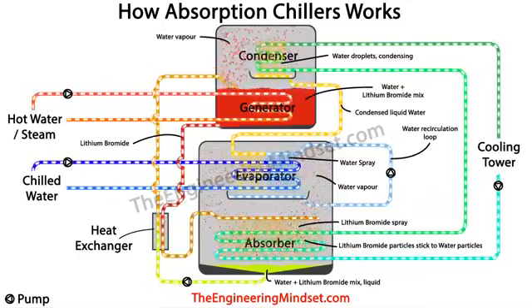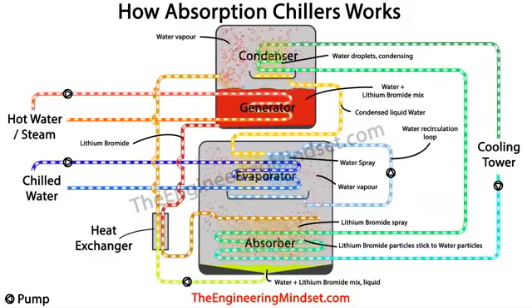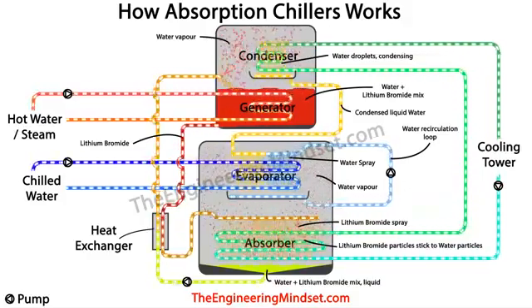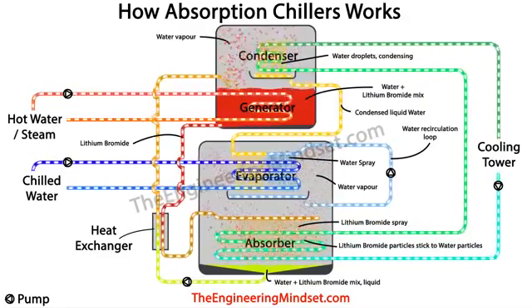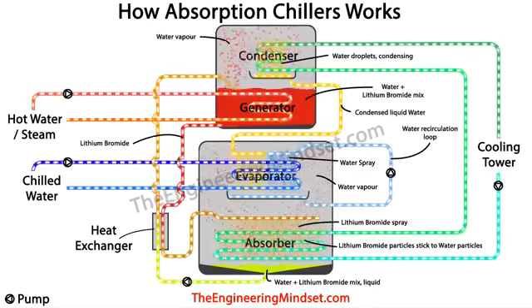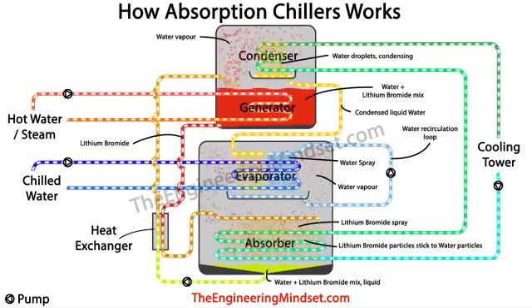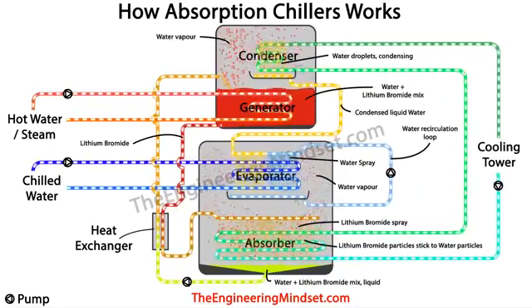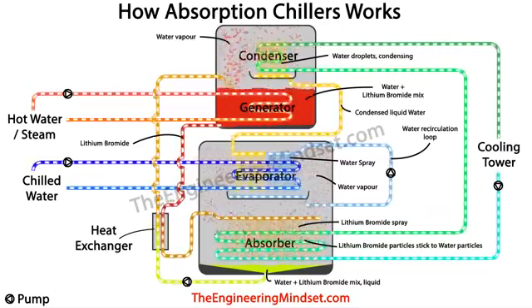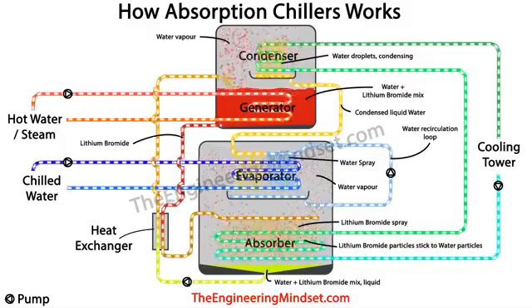Now the cooling tower water will also condense any of the residual water vapor particles or the lithium bromide particles and turn this back into a liquid. And once this has occurred, the mixture of lithium bromide and water is collected at the bottom of the tank in the bottom of the absorber, and it is now ready to be pumped back to the generator again to repeat the entire cycle. So there you have it. That's the basic operation of how an absorption chiller works. And that is the end of this video.